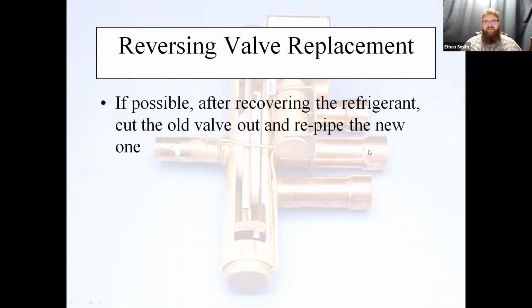So that allows you to braze the stubs onto the valve outside of the unit where you're not worried about melting coils or things like that. It also allows you to heat sink these pipes a lot easier when they're outside the unit versus inside the unit. Because remember, these seals in here are made out of Teflon. They've got to have thermal protection when you're brazing on them. So I will usually wrap rags around the base of each pipe. I'll also wrap rags around the body of the reversing valve and use water to keep those cool. Or if you've got some of that cool heat-conducting putty, you can actually jam it into all these nooks and crannies and get all that heat away from the valve body when you're welding.